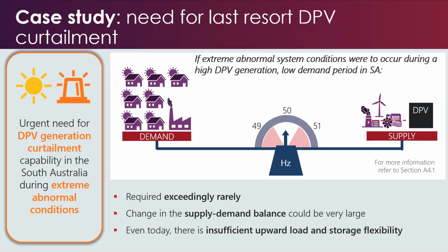Thanks, Rama. So now, once again, let's look at the supply-demand balance in this scenario. Eventually, as penetrations of DPV grow, we will see significant penetrations in the middle of the day, where DPV is generating at its maximum. In the case where we have a loss of interconnection to other regions, we have no options to export this excess DPV generation. This means that all supply and demand needs to be covered within a region itself, which can occur in South Australia when it becomes islanded. So in this case, there is high instantaneous penetration of DPV and low demand, as you can see with the DPV black box growing. Once again, this is represented on the supply side as they act as generators. To accommodate this much DPV in the system, we then curtail or turn off other large-scale generators that are supplying generation so that we can match the remaining load.